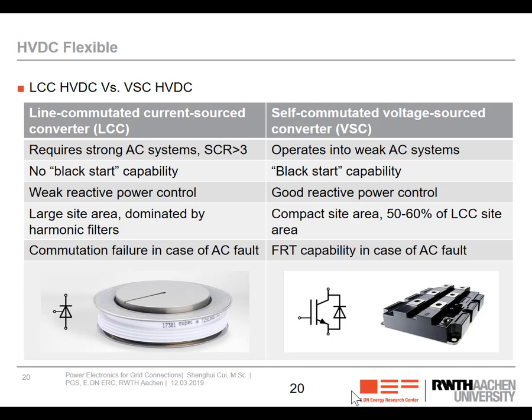But differently, voltage source converter based HVDC can operate very freely into weak AC grids, so there is no requirement for the SCR, the short circuit ratio, at all. It is also capable of black start, which means it can feed a fully passive grid. It has perfect reactive power control capability, and compared to the LCC technology, it has a very compact site area. One of the most important points is the so-called fault ride-through capability in case of AC fault. Even if an AC fault occurs, no commutation failure happens, and such a system is very robust against AC grid faults.